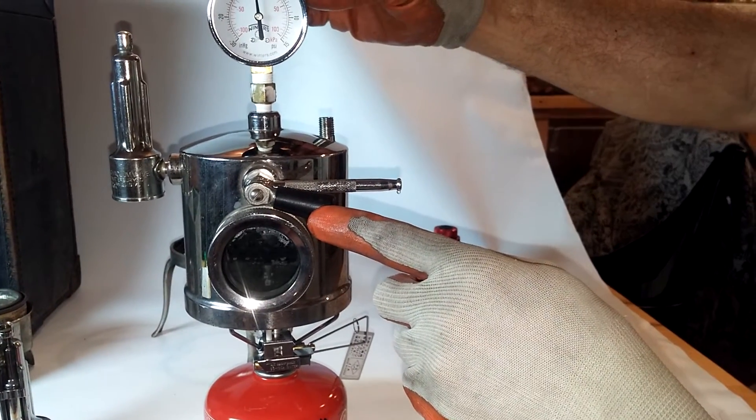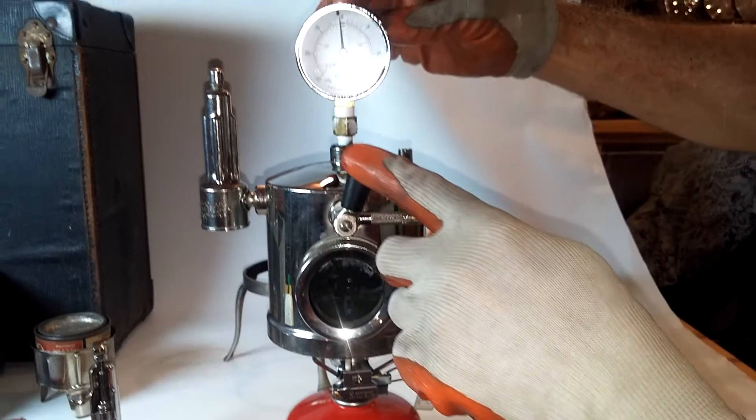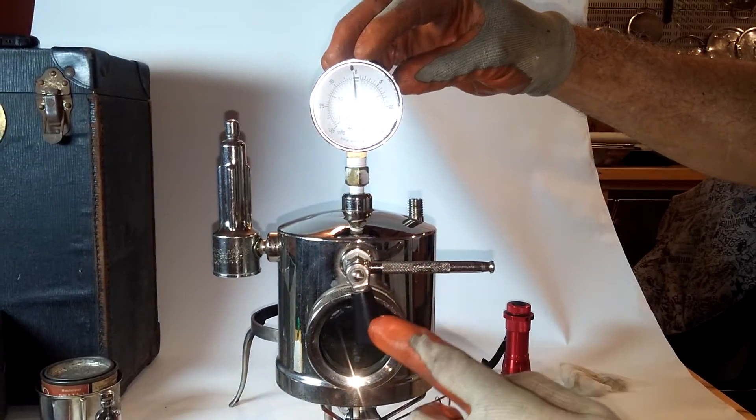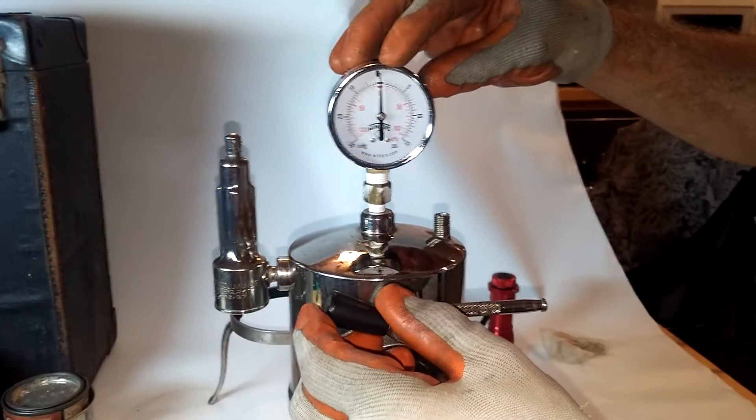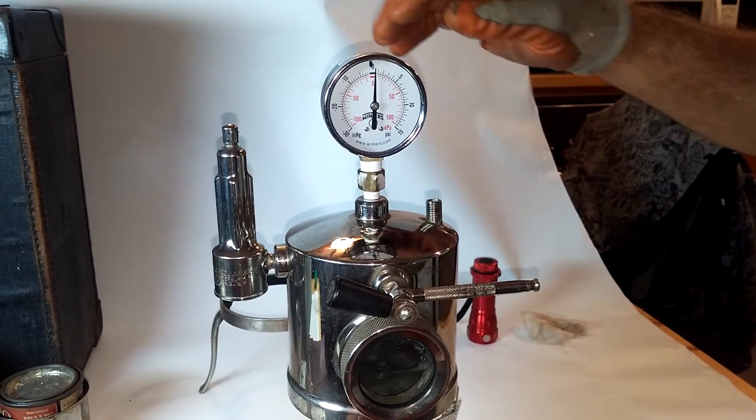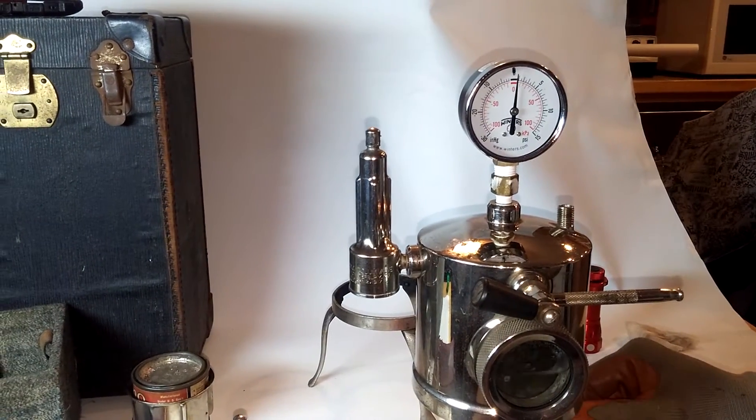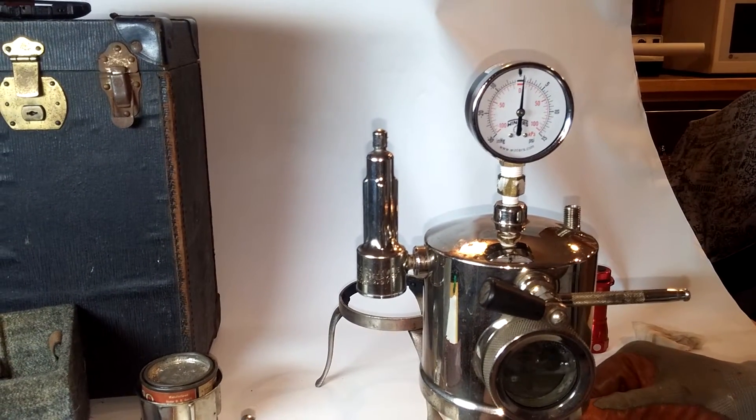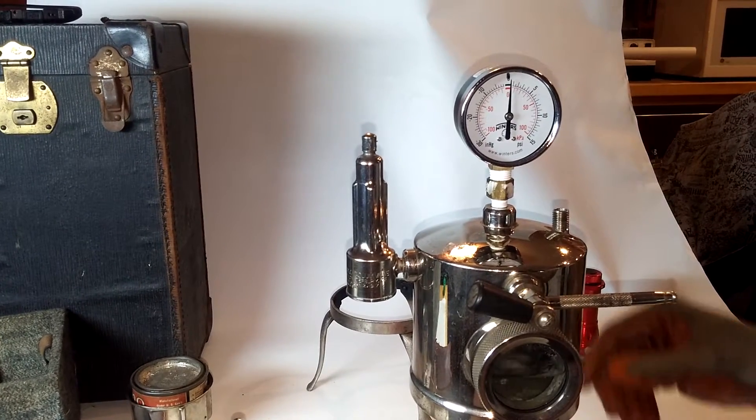A good head of steam there. We start to shut this Bakelite valve, and you'll see some pressure start to be generated on the gauge. And you'll see that the number two valve has failed, and does not shut against pressure anymore.